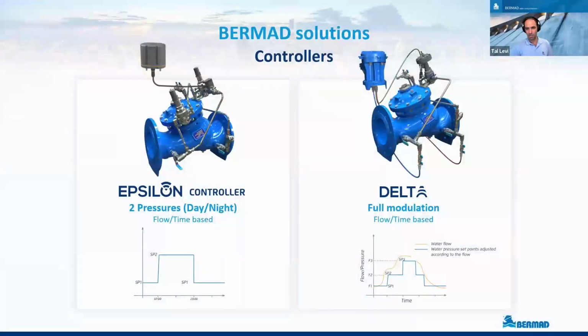So the solutions themselves: we are talking about two different types of controllers. The first one, on the left side, is what the market calls a day-night controller, which just switches between low pressure pilot and high pressure pilot, so night pressure and day pressure, achieving some of the pressure management goals. It will definitely reduce leakage, and that's a concept which is more economic and popular in some places. More advanced, the delta controller can do it based on flow rate, getting an indication from a meter and changing the set point, or based on time.